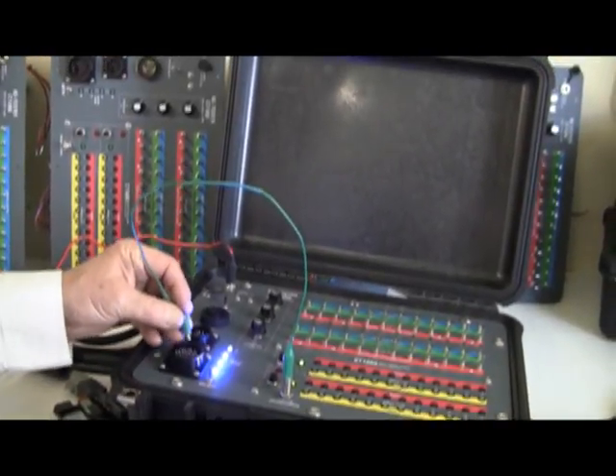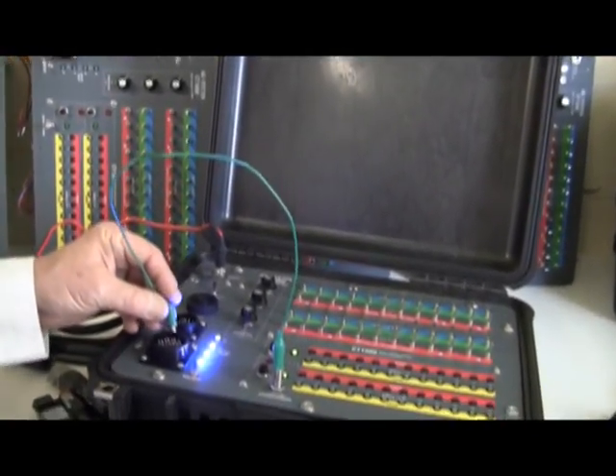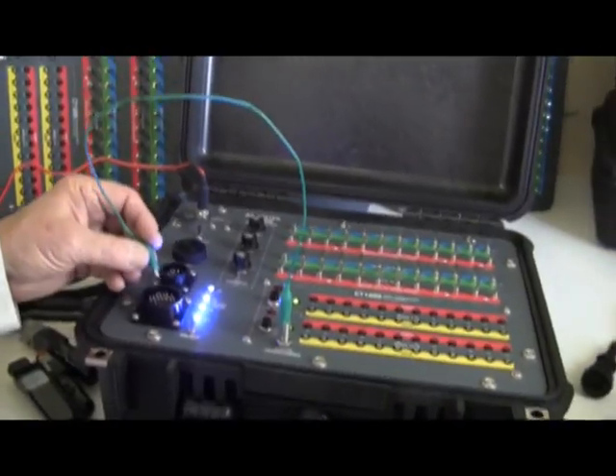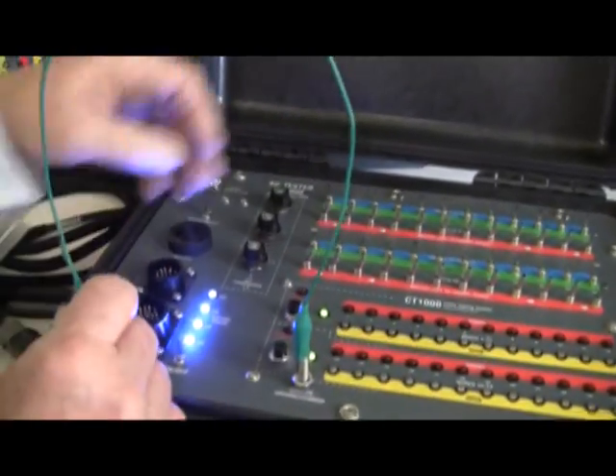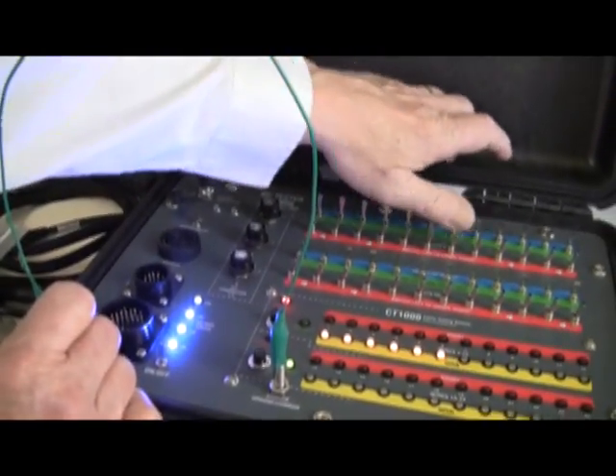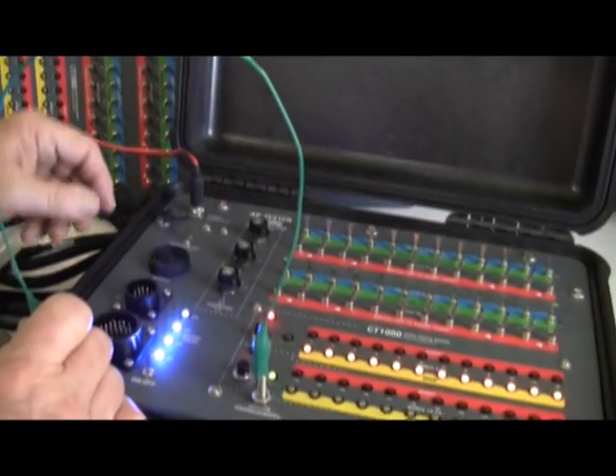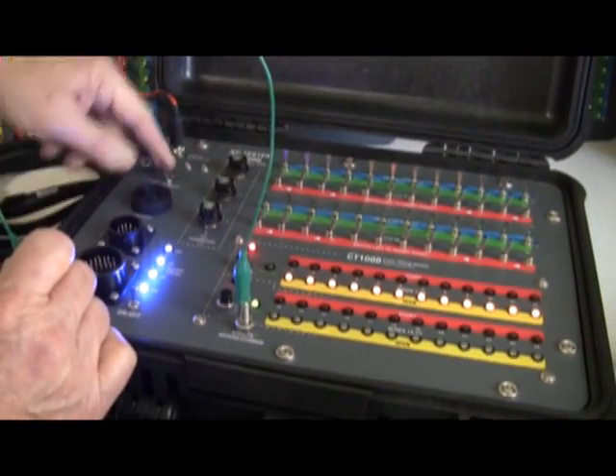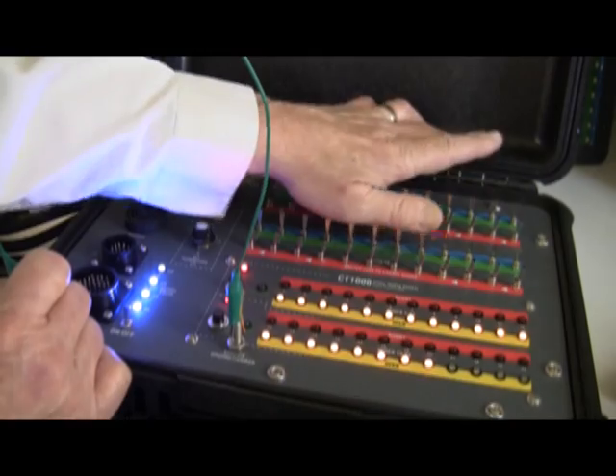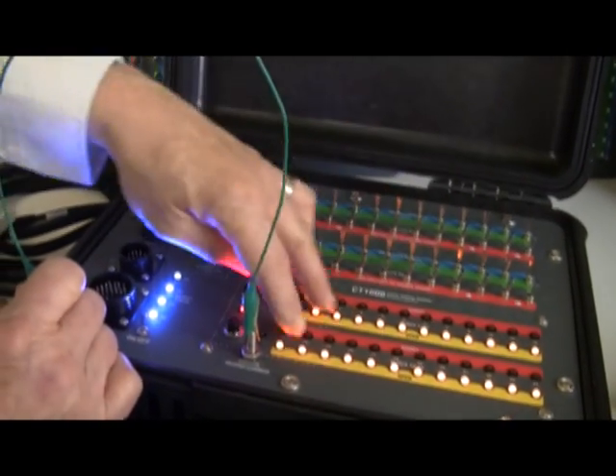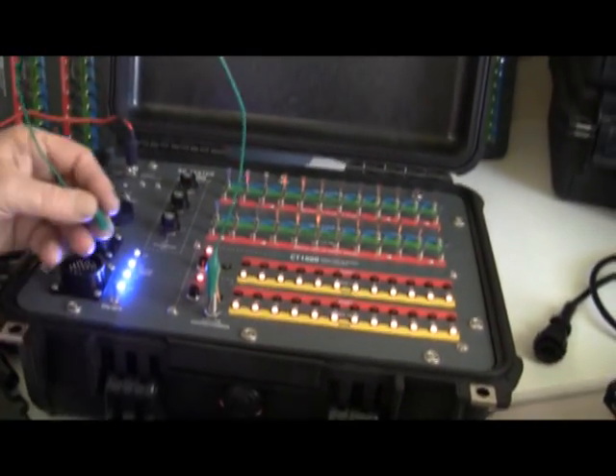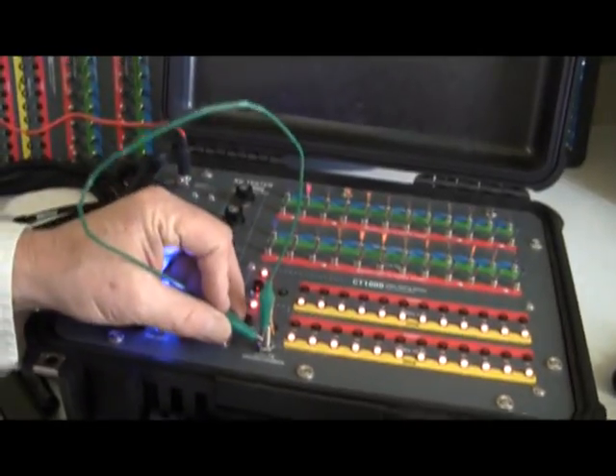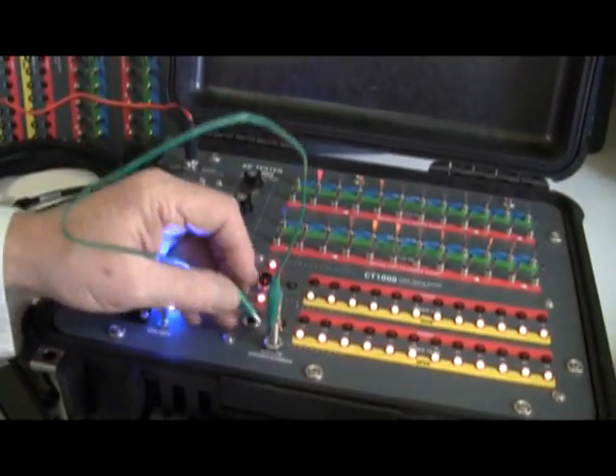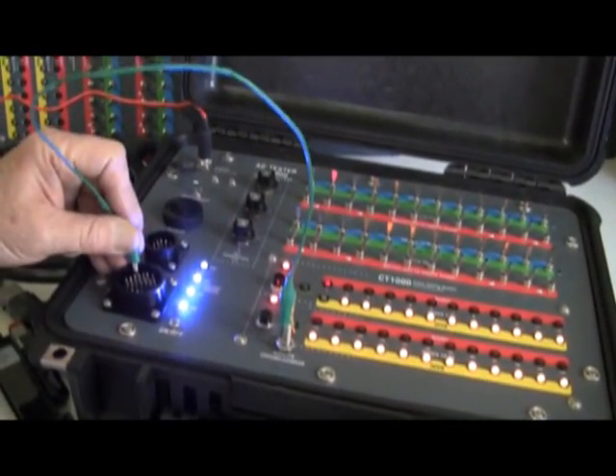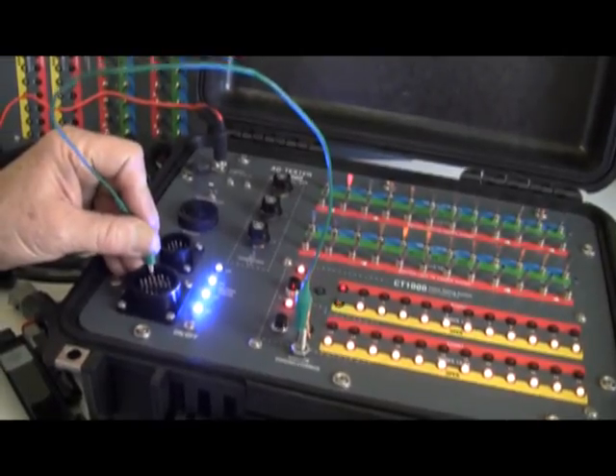Each of these connectors is numbered 1 through 37, and you can look closely inside. When we tell the system we want to test all of these, I'll go ahead and kill the sounder. Right now, all of these wires are opens. So if I take a jumper wire, go from the common or chassis ground, and touch wire number 1 or pin number 1...